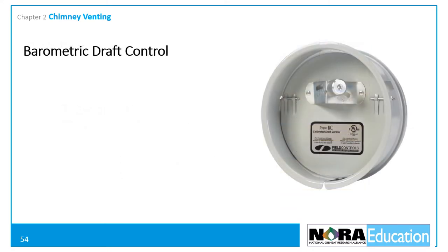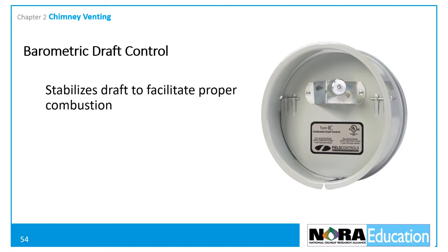This next section covers barometric draft controls, also known as draft regulators. Oil heat systems require a steady draft. Once the appliance reaches steady-state efficiency, the draft over the fire must remain constant to allow for proper combustion and efficiency. Since natural draft varies depending on several factors including atmospheric pressure, temperature, and wind, barometric draft controls are needed to stabilize draft for most oil-fired appliances.